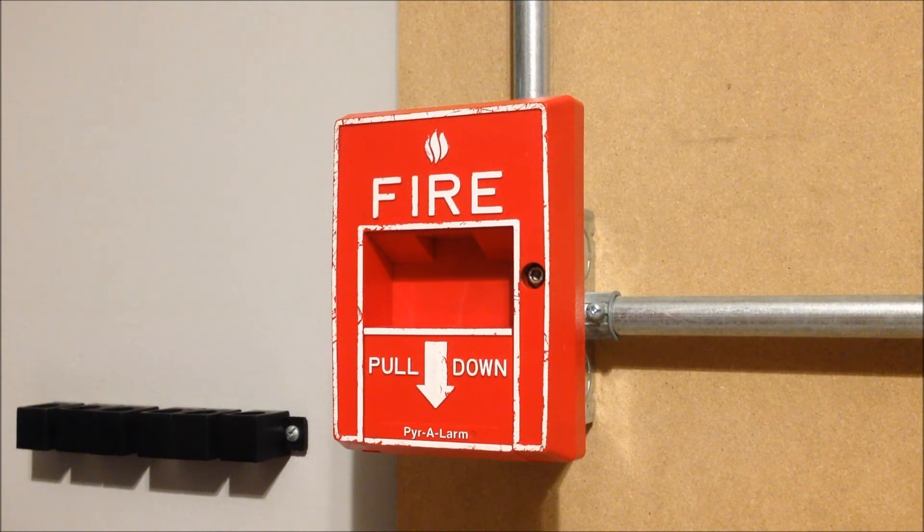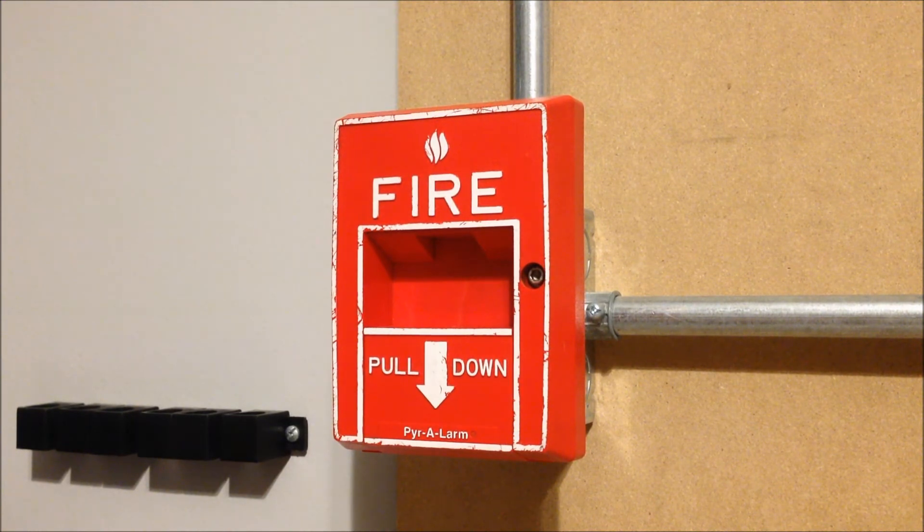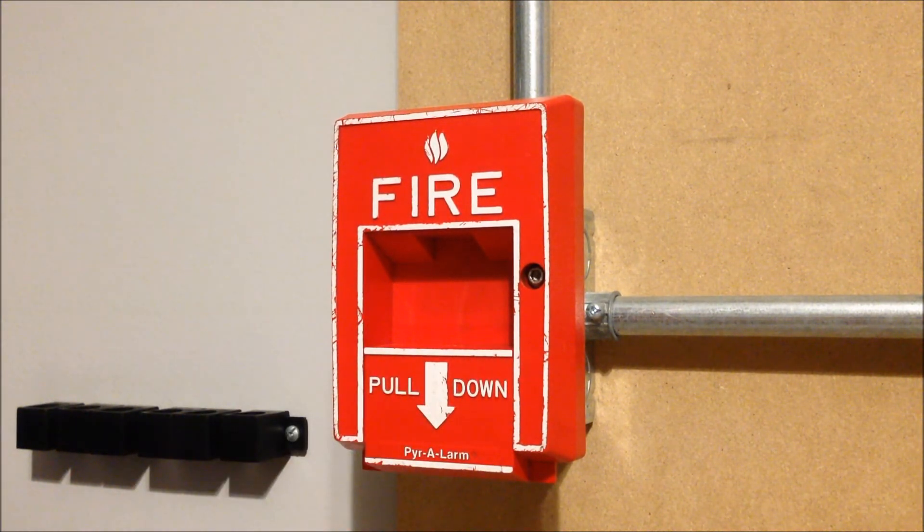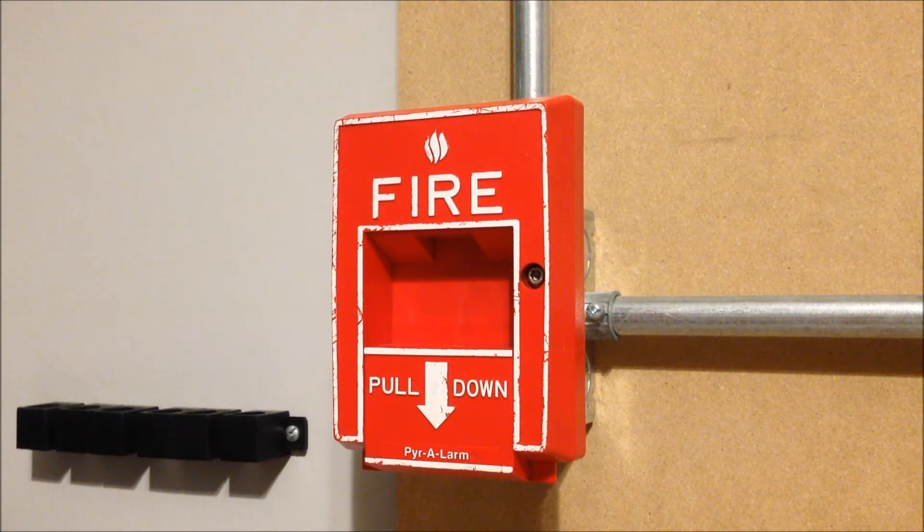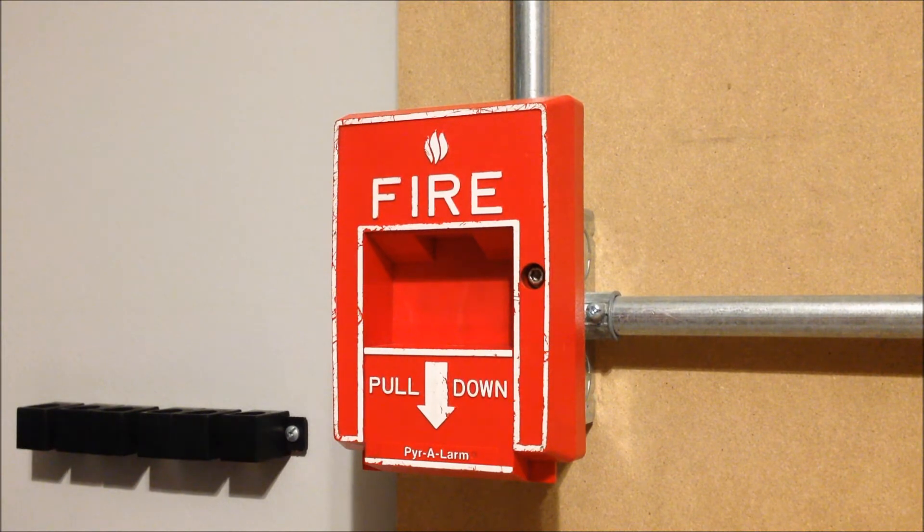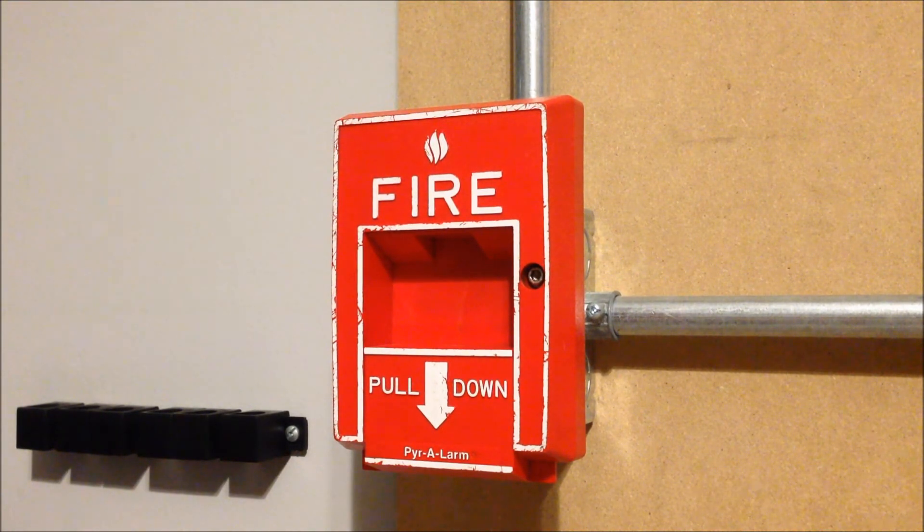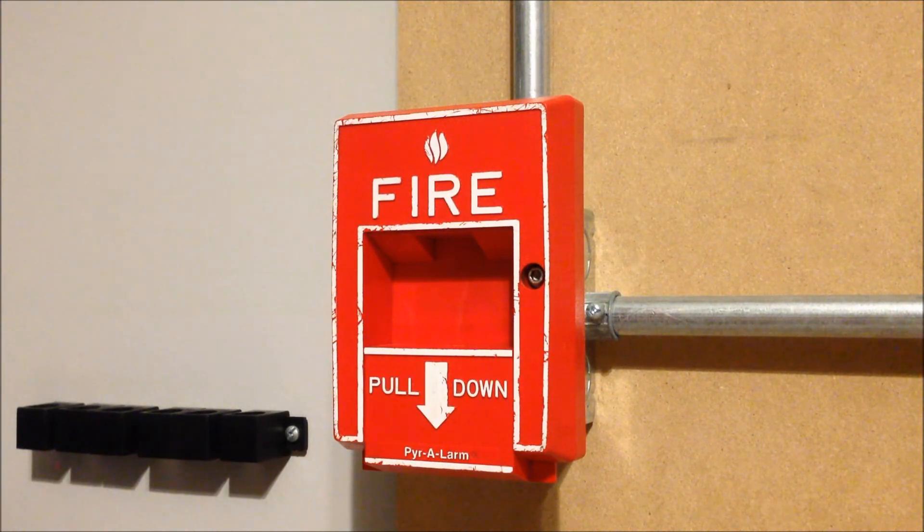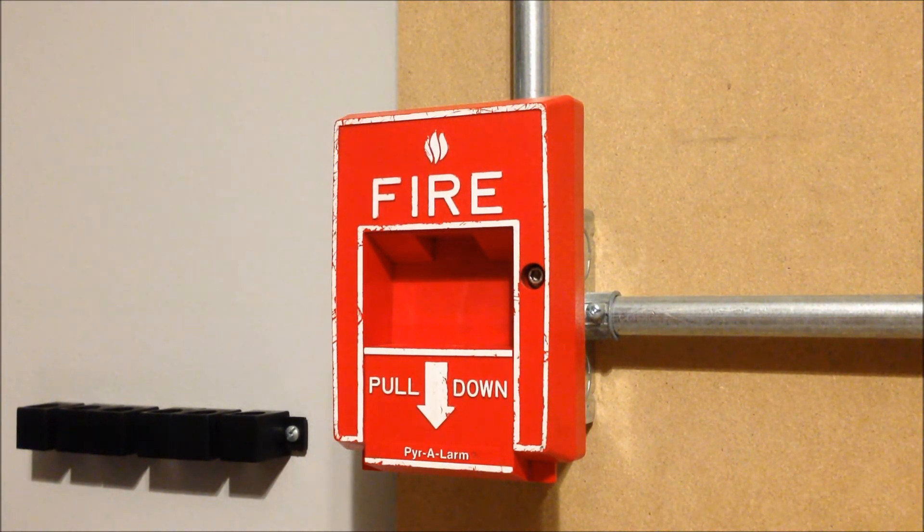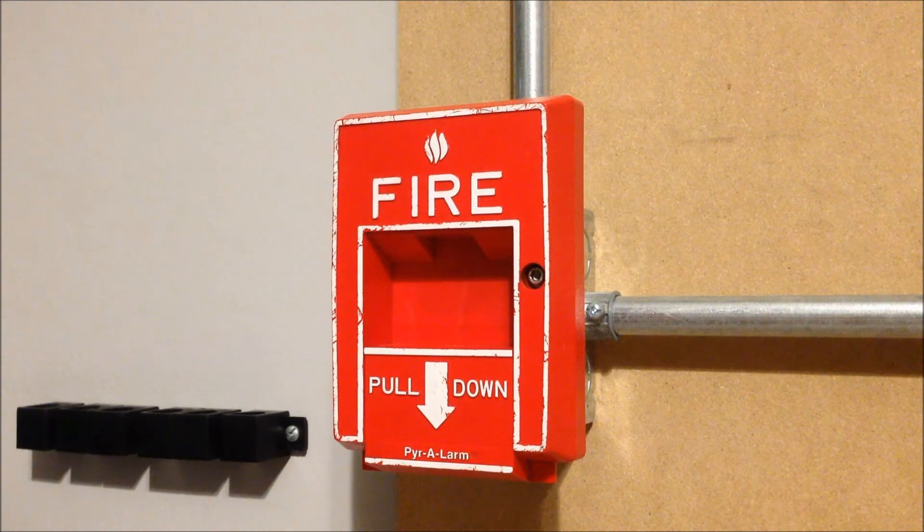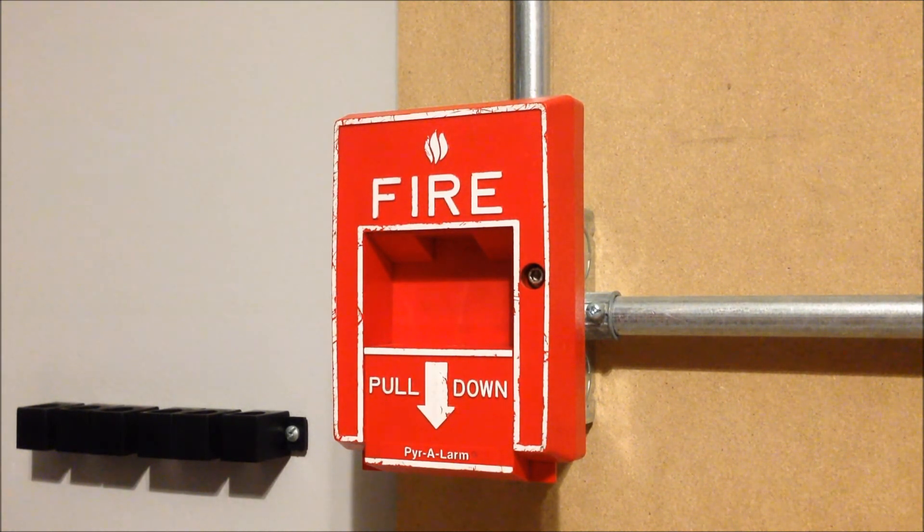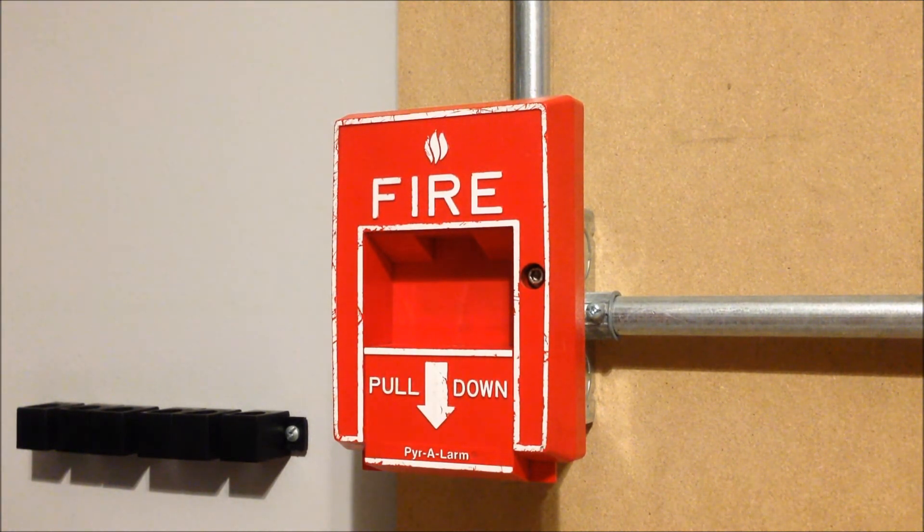So we're going to go ahead and start things off with the Pyrotronics MS5. So this pull station is wired into zone two so now you hear the chime pulsing out two tones every couple of seconds to indicate that zone two has alarmed on the system.